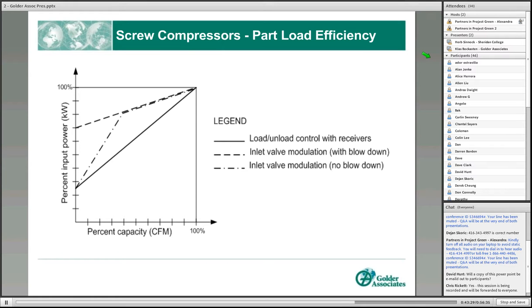And if you look at 50% of the CFM, and you go up to the solid curve, which is showing load-unload control systems, you're dealing with roughly about 60% of the full kilowatt on that compressor. If the compressor instead is an inlet valve modulation with blowdown, you're dealing with roughly about 80% of the kilowatt at 50% CFM. So you can see any part load is not very efficient or not very cost effective. You're ending up spending 80% of the full energy consumption by the compressor and only achieving about 50% of the CFM output.